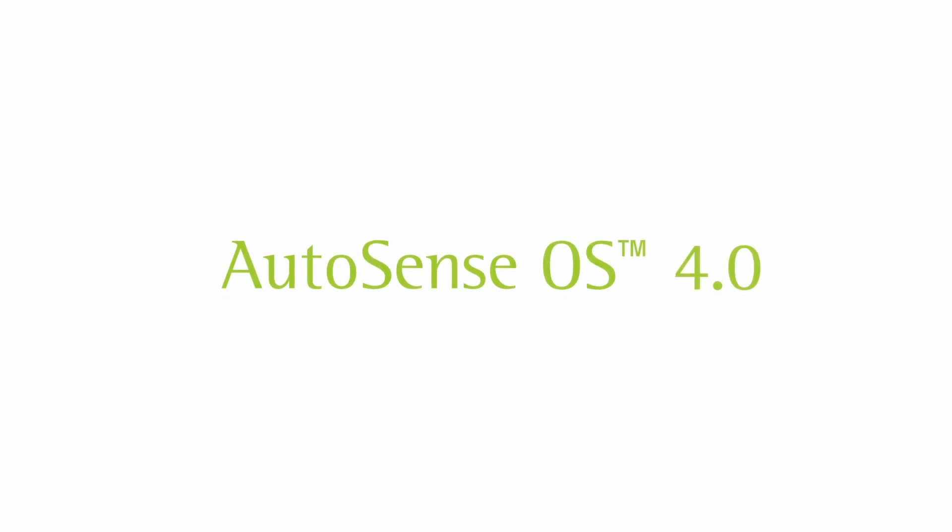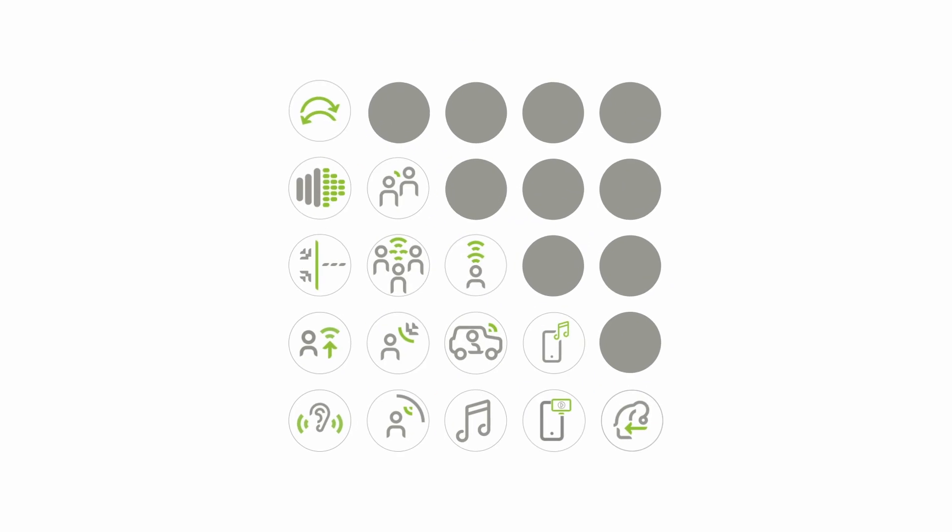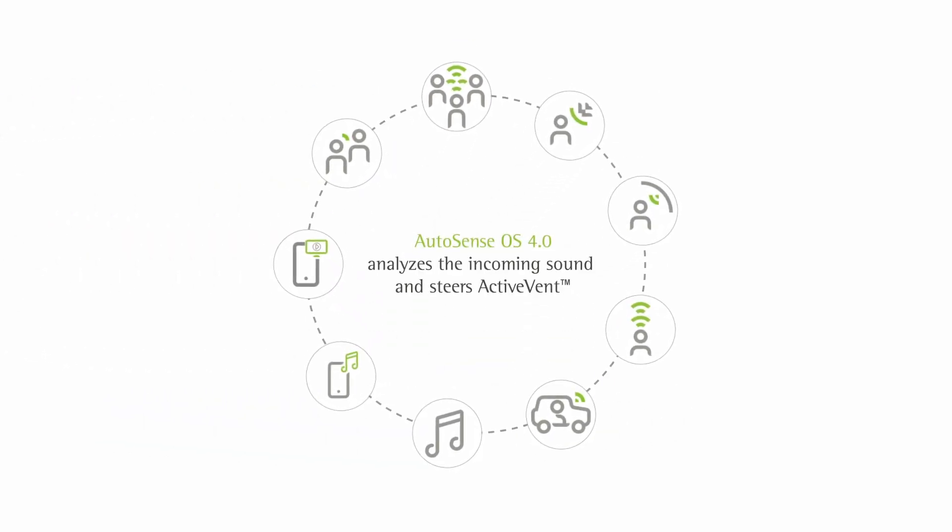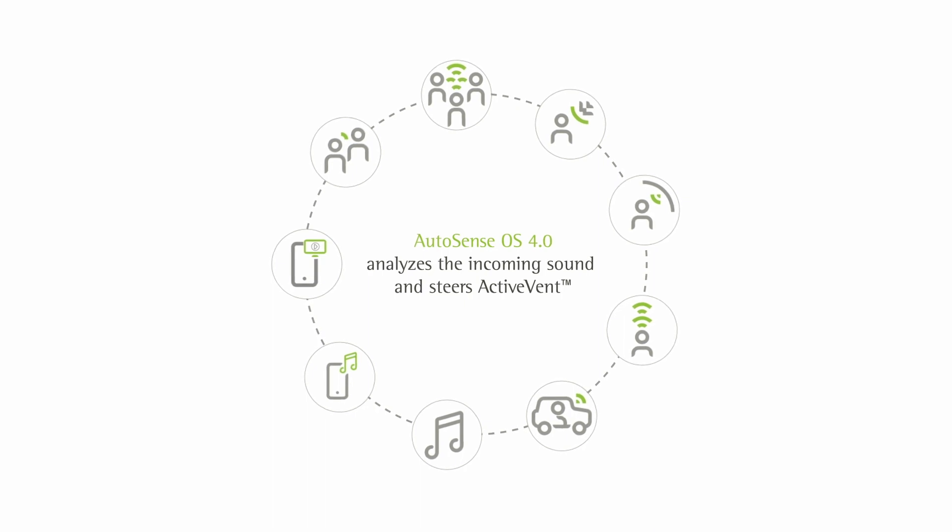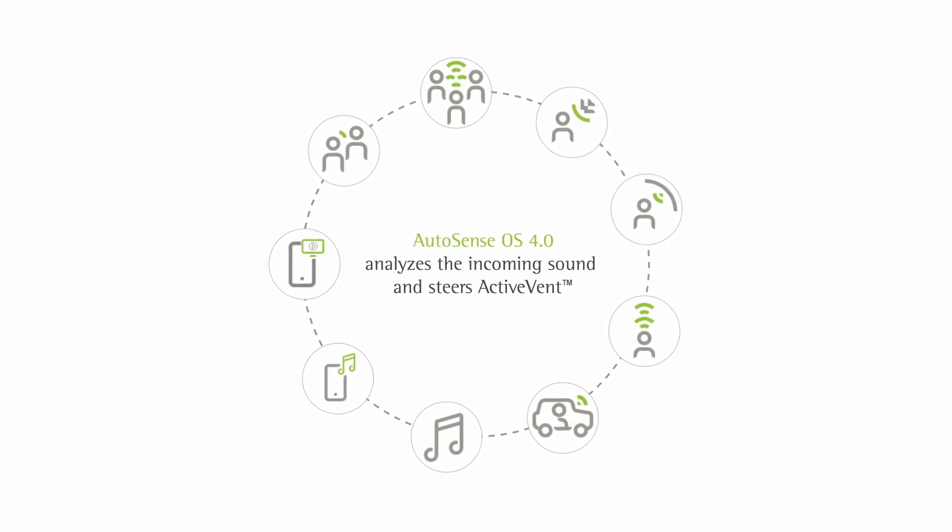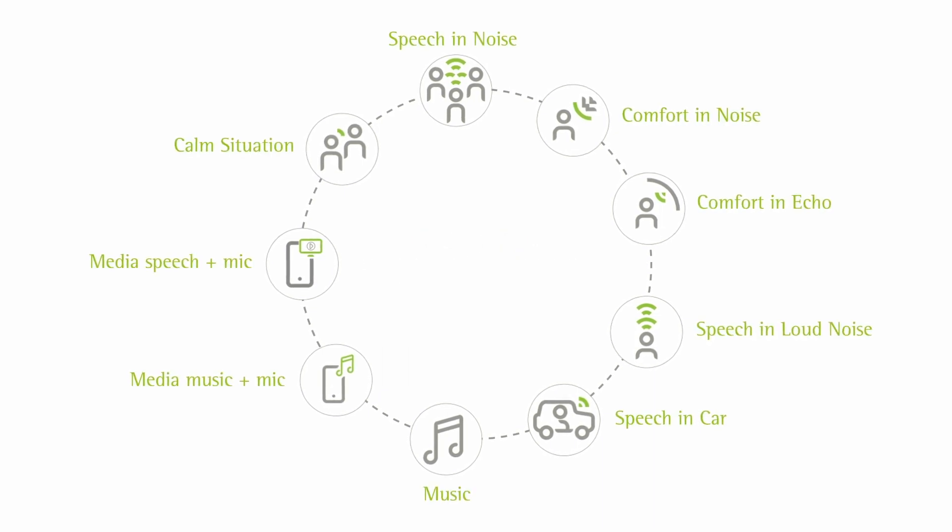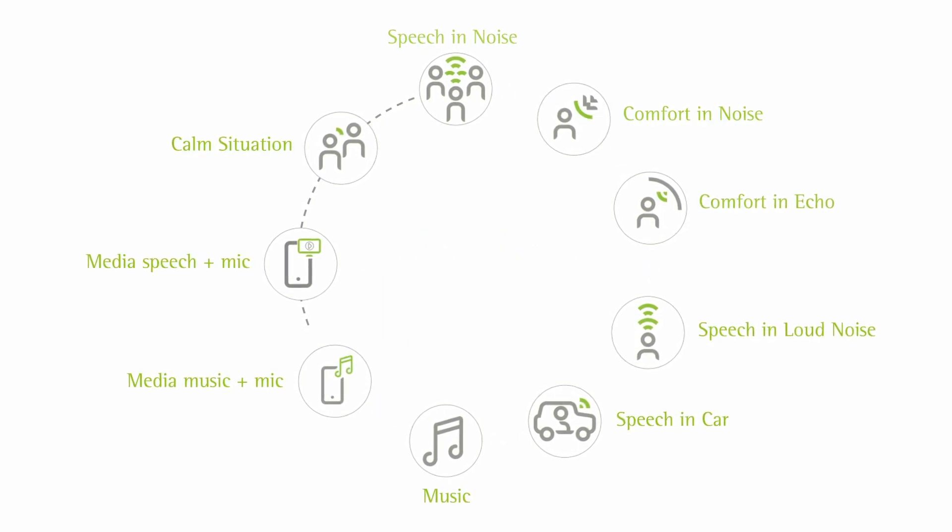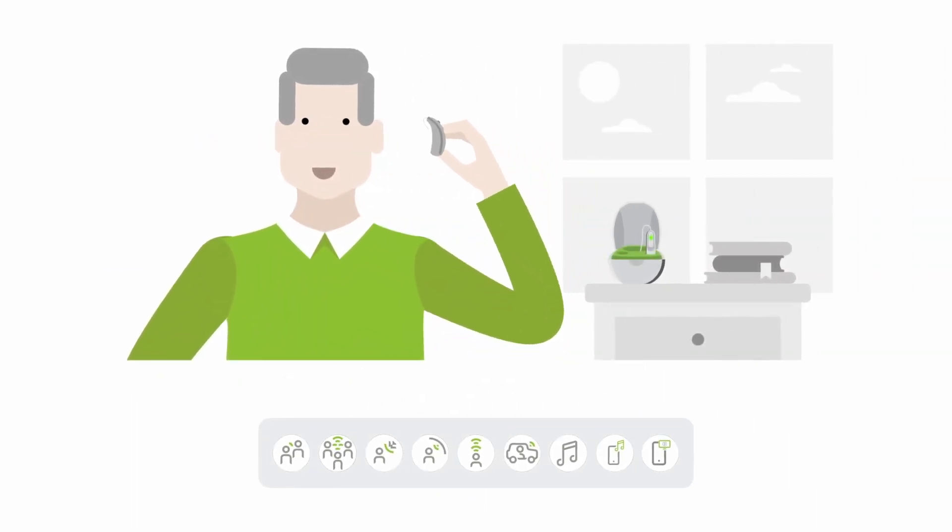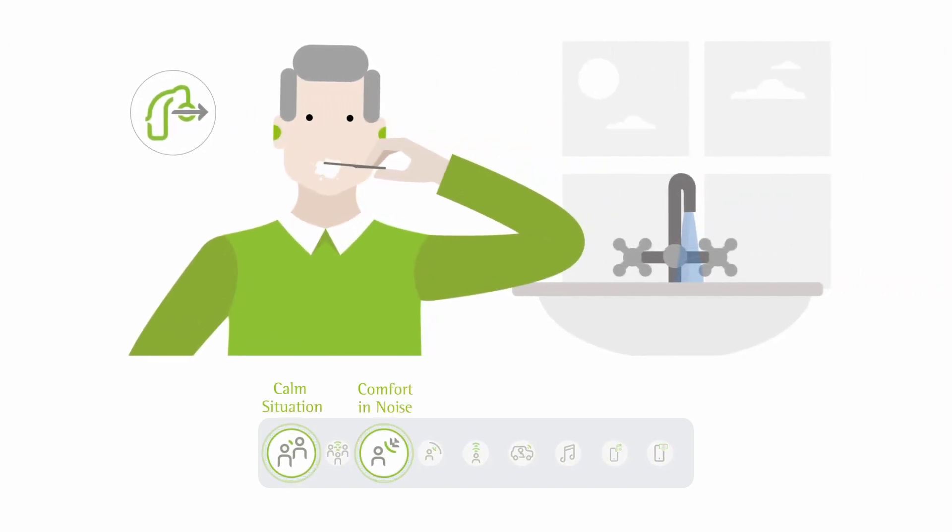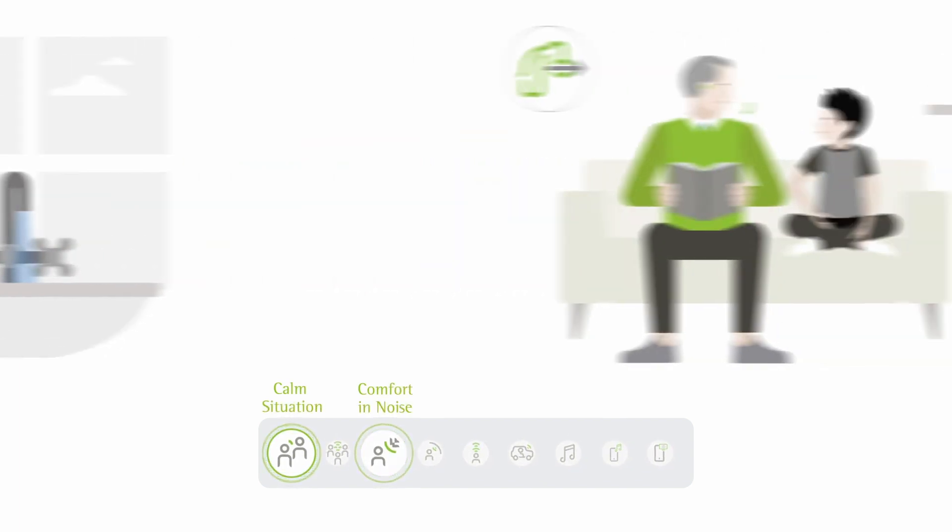The mechanical vent of ActiveVent is controlled by AutoSense OS 4.0, our automatic environment optimizer in all Phonak Paradise hearing devices. AutoSense OS 4.0 will tell the vent to open and close according to the listening environment. This brief animation will walk us through just a couple of examples of what this can look like. With the client wearing their Phonak Paradise hearing devices, when AutoSense OS 4.0 assesses the environment as a calm situation or a blended environment, the vent state will remain open.